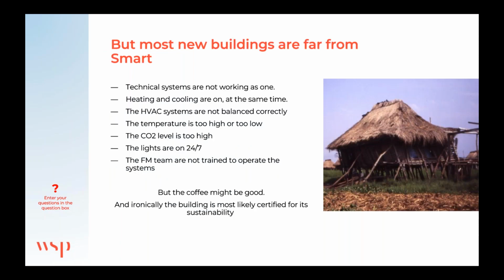But the fact is that most buildings are far from smart. The technical systems are not working, and not working together. The heating and cooling could be on at the same time, and often the HVAC system is not balanced correctly. So no matter how much equipment you put into them, they would never be able to control right.